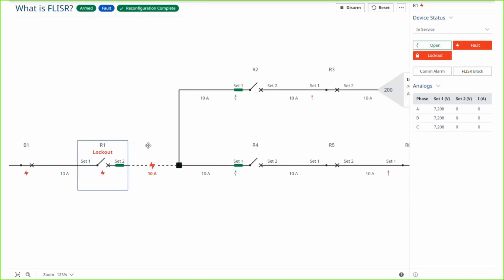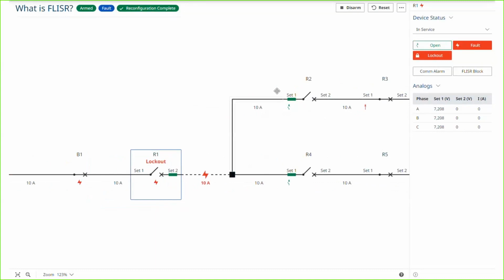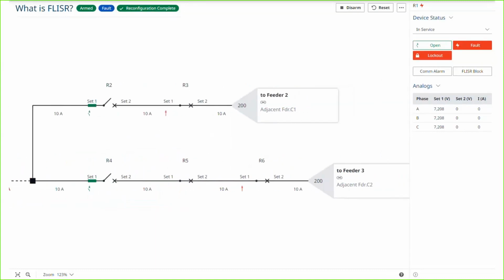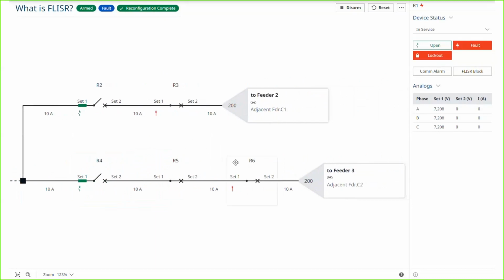We're able to make that outage as small as we can by isolating it, opening recloser 2 and 4, and shrinking what we call the fault boundary, the boundary of devices upline and downline. Once we do that, we're able to restore all load that's not unfortunate enough to be in the same zone as the fault using adjacent circuits. So you have feeder 2 and feeder 3 over on the right that were available to assist.